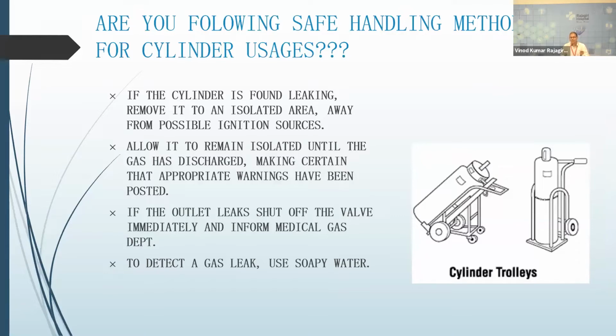It could be leakage from the shut-off valve, where we can close the valve. But if it is a cylinder leaking, then you need to isolate it to a location that is safe from any combustible or ignition source, where you have control and there is no possibility of a fire happening. Every time the cylinders are removed and installed into the manifold room or into the equipment, leakage has to be tested. Use soap water to test it. These are simple methods that are generally missing when the cylinders are being replaced.